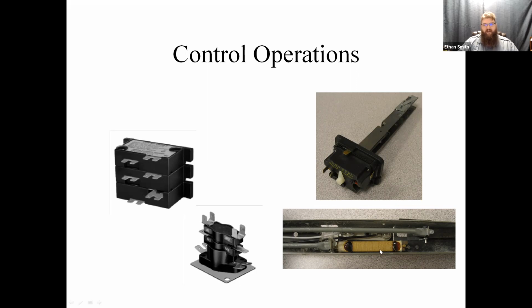Okay, you just thought it was a high temperature limit in a really old furnace. Nope, it's got an electric heater in it. Okay. We couldn't rely on it. It wasn't 100% reliable to get enough radiant heat to trip, and so we had to bias it a little bit. So it's got a little electric heater up inside that camstat.